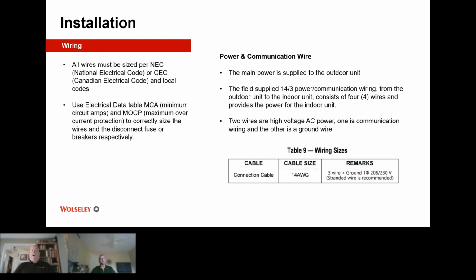We want to make sure that the cable or the wire coming from our electrical box is the right field-supplied power and communication wire. Now, when I talk about that, we've got a slide coming up here, but there is mini split cable, which is a 14-4 stranded and shielded wire for the outdoor to indoor unit connection. And then there are other RS-485 communication cables. There are other communication cables that are a 14-4 or 14-3, three of those being power connections and one of them being a communication connection. Always make sure you consult your brand manual to make sure that you are using the required size.